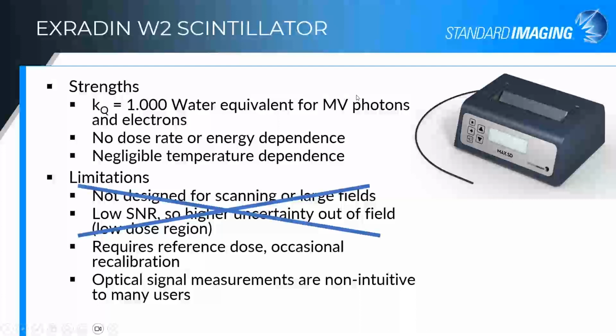Good questions. Thank you for that. Strengths of the W2 really are exactly the same as the W1. It's the same fiber, it's the same analysis method. It just happens to be that we've got those dedicated electronics for it. So we still have that KQ of 1. We still have no dose rate or energy dependence. We still have that same teeny tiny little bit of temperature dependence, so you can ignore it for QA measurements. What we've done with the W2, though, is removed a couple of the limitations that we had with the W1. This is designed for scanning, and it has a better signal to noise ratio, so that out of field measurement to get the tails of your penumbra is much more accurate with the W2.